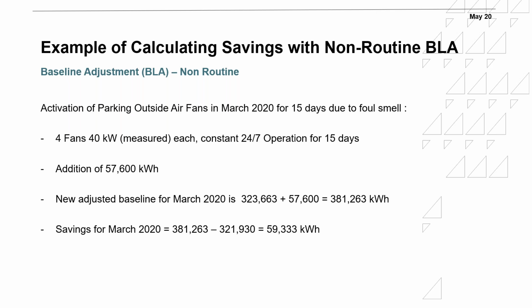Again, for us to estimate the consumption, better to do the measurement on the fan to see what is the actual consumption. It's a constant speed fan. I don't need to really log it for a long time. I can log it for, let's say, 15 minutes and see what is the consumption. 4 fans times 40 kilowatt for 15 days will equate to around 57,600. So for my adjusted baseline, I need to go back, take the adjusted baseline from the weather factor, and add to that 57,600. That would be the new adjusted baseline.